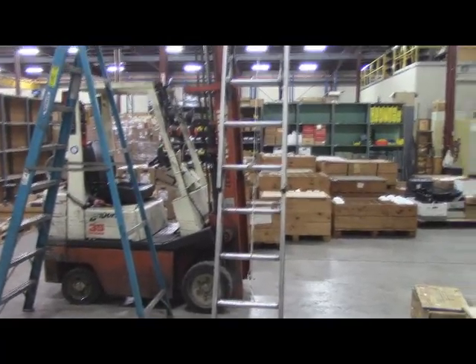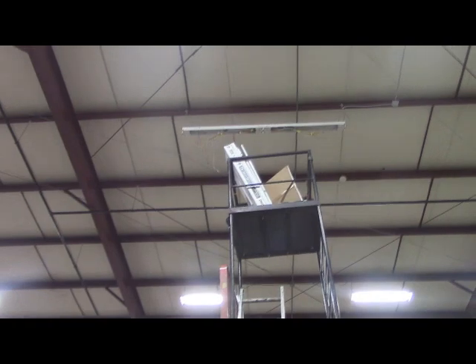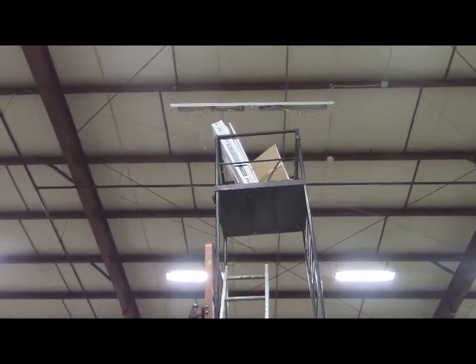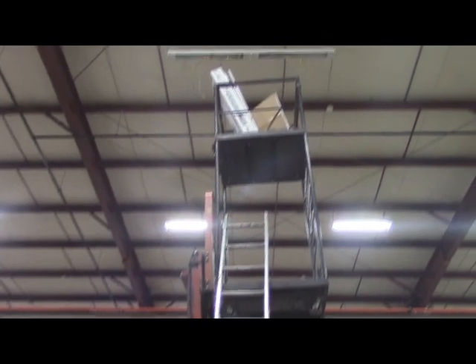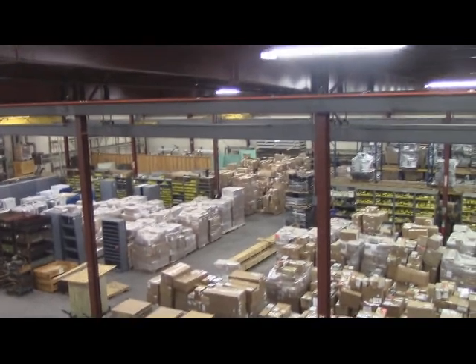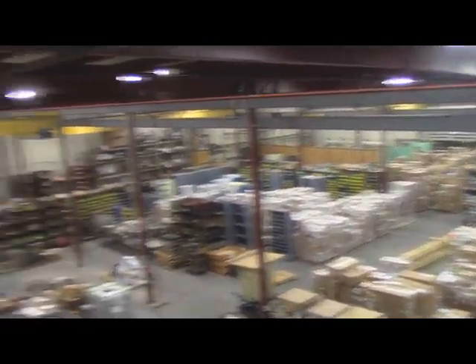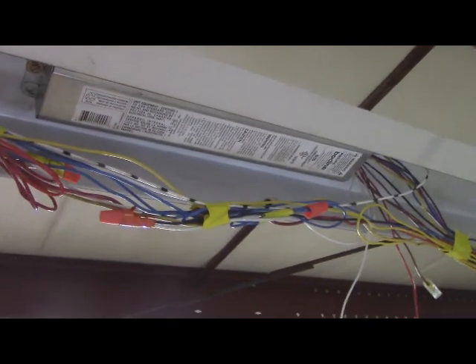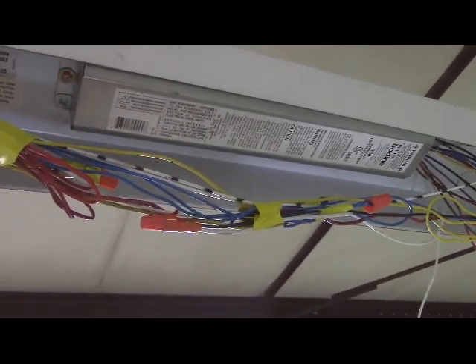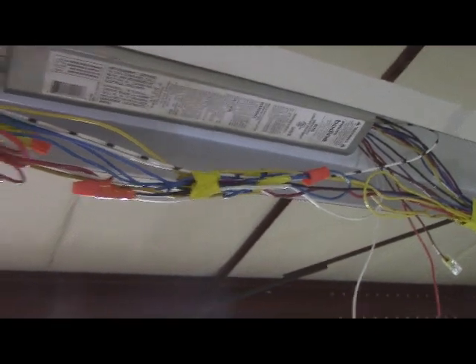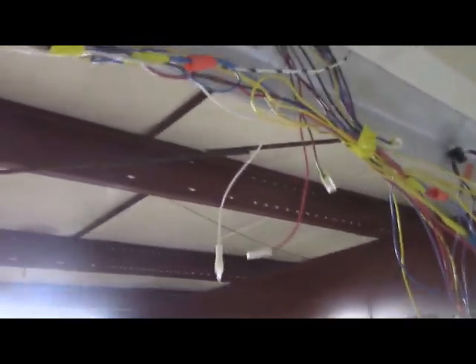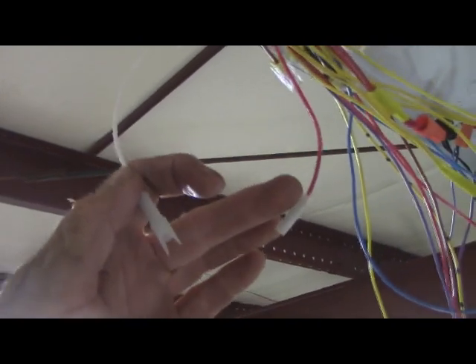Okay, and this is my high reach apparatus going up there to do that light fixture, change out that emergency ballast. I go to that platform and then up to the next. Okay, we are up top now, and nice view from up here. Okay, now there's our nice new emergency ballast, Bodine B50, and I have it wired. As you can see, quite a bit of wiring between that and the instant start 4-bulb electronic starter.